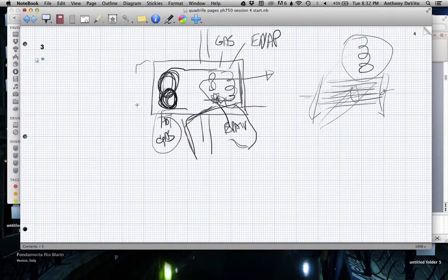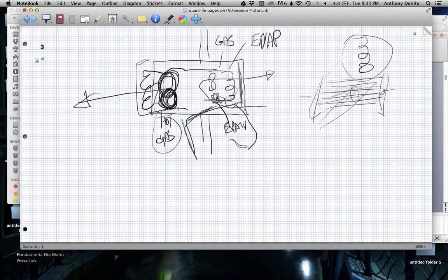Now you have to take that hot gas and turn it into a liquid. And the way that you do that is you take the compressed gas, you send it into another coil called a condensing coil. And you put a fan back there and you blow air over that coil. That takes the heat away from that hot gas and turns it back into a liquid. And now you reuse that. That's your refrigeration cycle inside a window air conditioning unit. Okay? And that goes on and on and on.